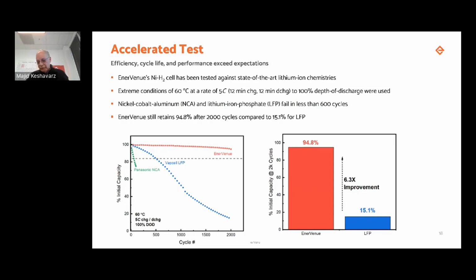We went even further to conduct some other accelerated tests. We ran the battery at 60 degrees C, at 5C charge, 5C discharge, 100% depth of discharge. So 0 to 100, going back and forth at 60 degrees C. At the same time, under same conditions, we picked 2 types of lithium-ion batteries, one NCA from Panasonic and one LFP. From the graph, it is clear that NCA reaches 80% of its initial capacity after 70 cycles, the green dots. LFP did much better. It lasts 600 cycles. It takes 600 cycles to get to 80% of its capacity.